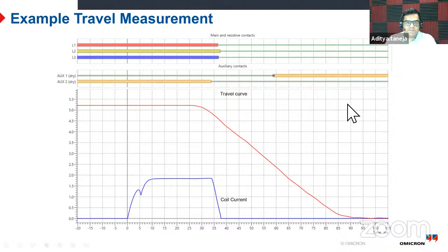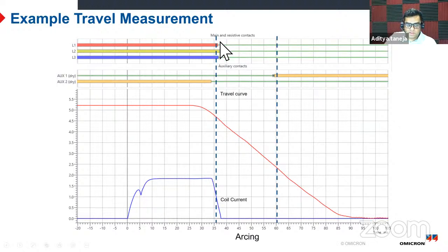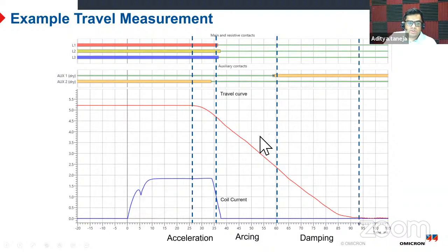Now, when we do the analysis, we want to know the speed of the arcing contact, or the speed of the breaker during the arcing period. That's most important, and that happens when the breaker contacts open and for some more time, because in real-life conditions there will be arcing happening there. So there is a phase where it accelerates and a phase where it dampens, it slows down.